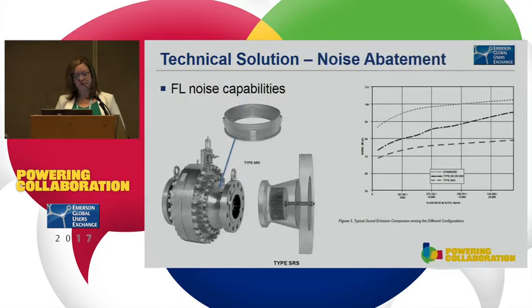Looking at the noise a little closer, you'll see here this is the SRS trim. It fits right in the body here, so you don't see it — it's part of the flow path. It's drilled hole, splitting up that gas flow to allow for a lot of noise abatement, separating out that noise and making a bunch of small little paths.